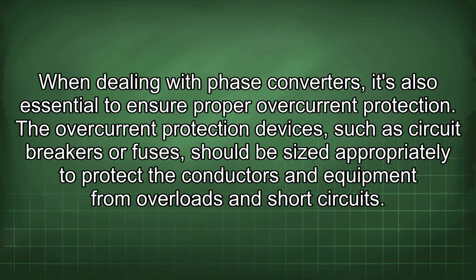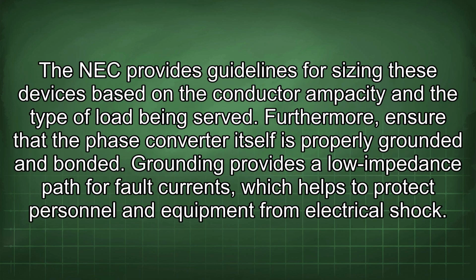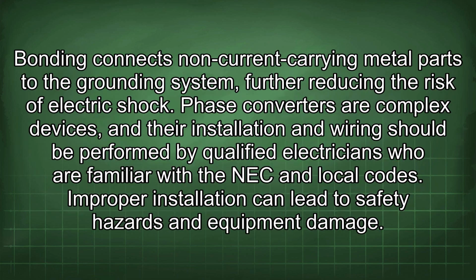When dealing with phase converters, it's also essential to ensure proper overcurrent protection. The overcurrent protection devices, such as circuit breakers or fuses, should be sized appropriately to protect the conductors and equipment from overloads and short circuits. The NEC provides guidelines for sizing these devices based on the conductor ampacity and the type of load being served. Furthermore, ensure that the phase converter itself is properly grounded and bonded. Grounding provides a low impedance path for fault currents, which helps to protect personnel and equipment from electrical shock. Bonding connects non-current carrying metal parts to the grounding system, further reducing the risk of electric shock.